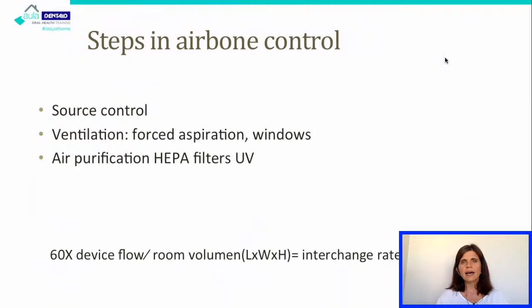It's very important to know that a lot of people are buying a lot of devices without any proven activity. So for any device you buy, there is a formula, which is written here: 60 times the device flow, divided by the room volume, gives us the air exchange rate per hour, and it's important to make sure it is a minimum of 6 times per hour.